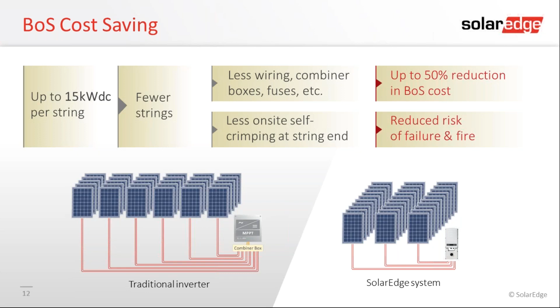It was a 204.6 kilowatt DC traditional string 1000 volt string inverter versus SolarEdge. Your AC power 168 kilowatts versus 166.5 kilowatts. So they beat us on the AC power rating. The DC to AC ratio was comparable, 1.22 to 1.23. Same number of modules, and we were able to do this with 2 inverters versus 7 inverters, right? So number of strings went from 33 to 15, so we have 50% less number of strings. So our modules per strings went up, so they basically doubled, 44 versus 20. So our DC cable length dropped by half almost, 5,692 feet of copper versus 10,000 feet of copper.